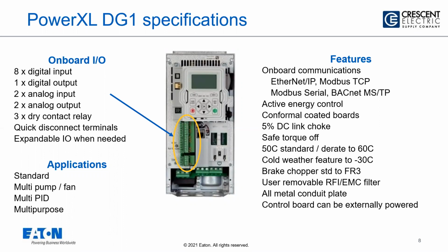We do put brake choppers into each one of these units, so our frame 3 or 40 horsepower and below are going to have a brake chopper standard, and that can then be added at the higher units. It's an all metal conduit plate, so you can see on the bottom where the holes where the conduits come in. Very robust, rugged conduit plate.